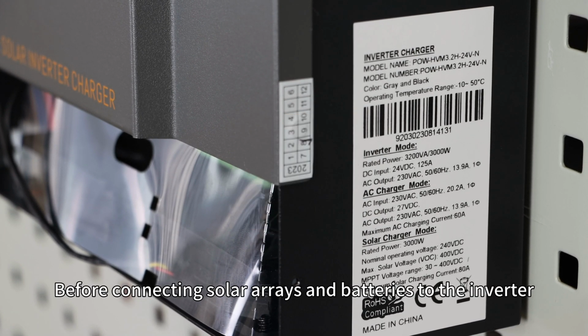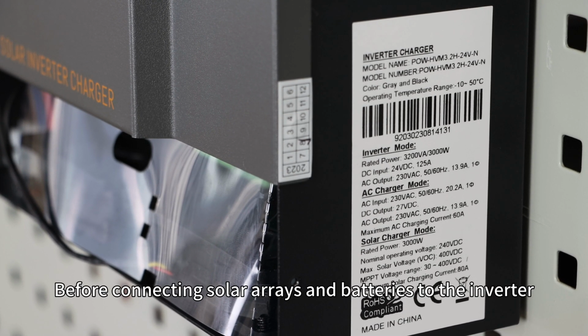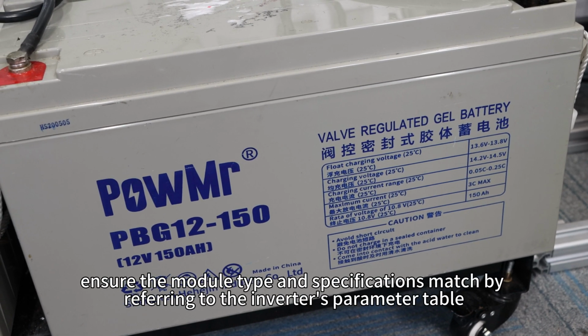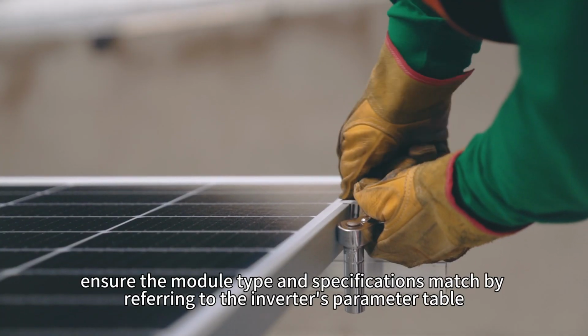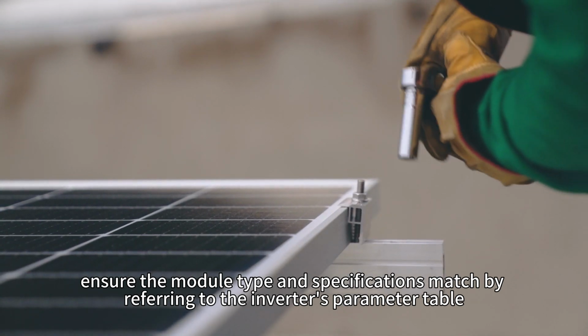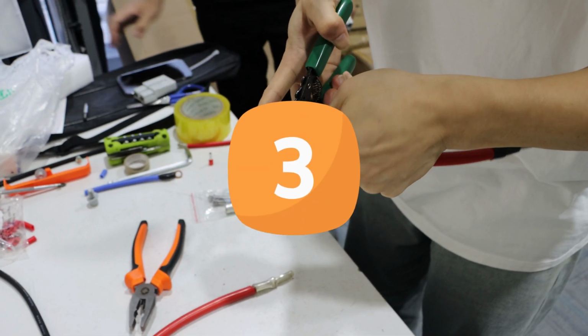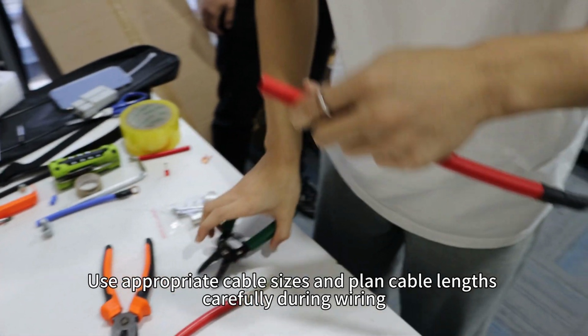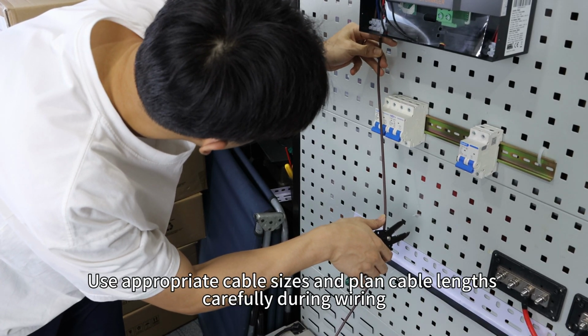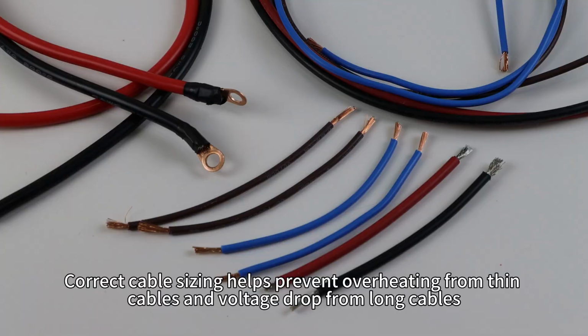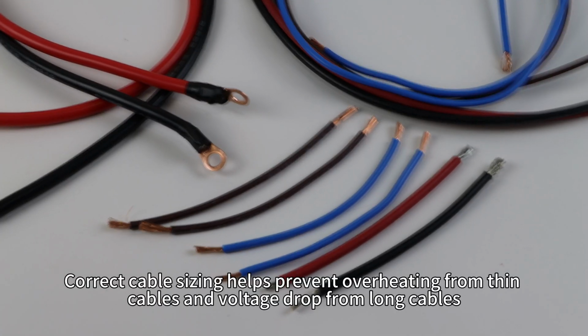Before connecting solar arrays and batteries to the inverter, ensure the module type and specification match by referring to the inverter's parameter table. Use appropriate cable size and plan cable lengths carefully during wiring. Correct cable size helps prevent overheating from thin cables and voltage drop from long cables.